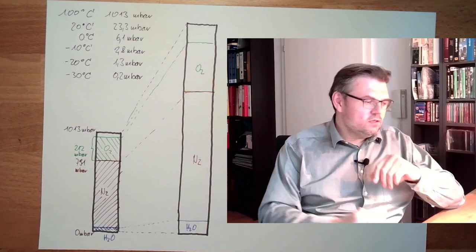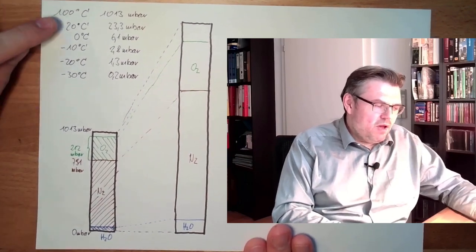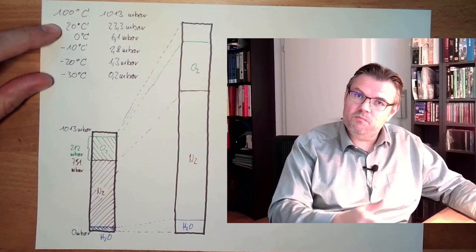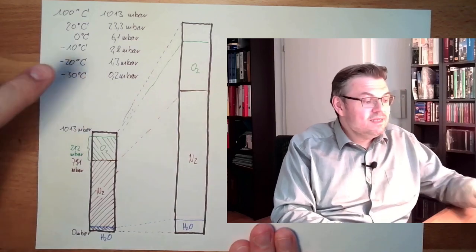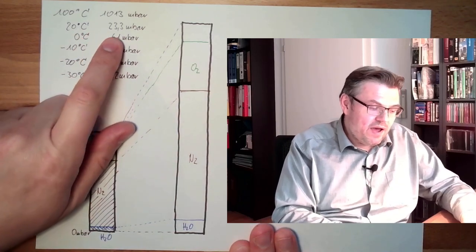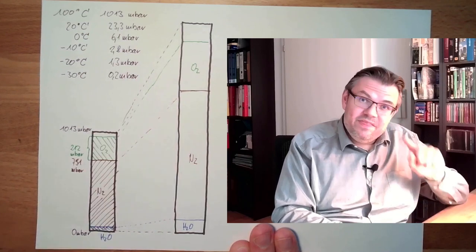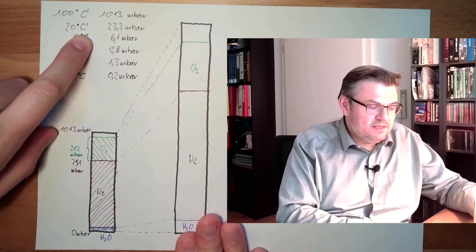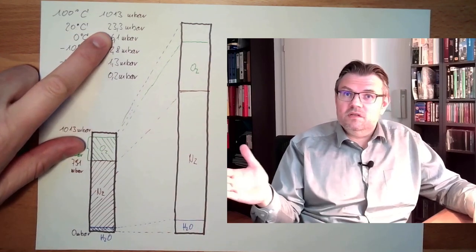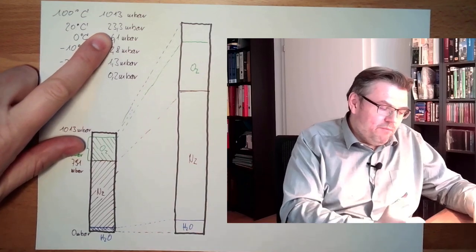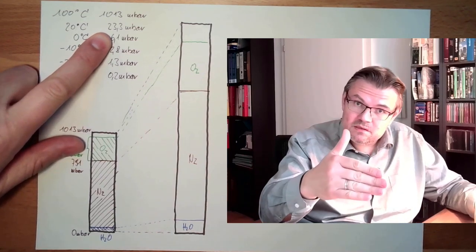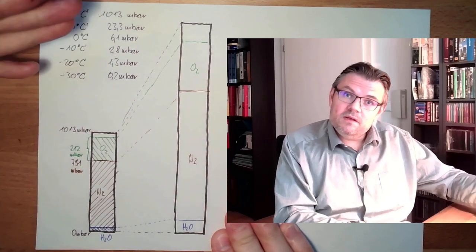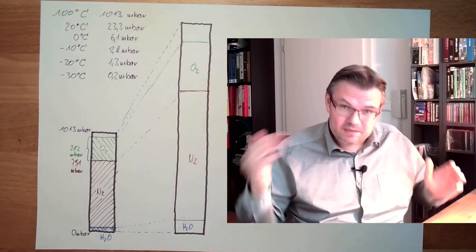Okay. So we say we have around the same temperature after the compressing. However, we have higher pressure. Since we have higher pressure, we also have a higher partial pressure of water, and this might lead to the fact that if I'm sucking in air with 20 degrees Celsius and let's say 20 millibars, there is no condensation at all. And then I'm doubling it, so I have 40 millibars of partial pressure. So the difference between 23 and 40, the 17 millibars, they need to condensate somewhere.